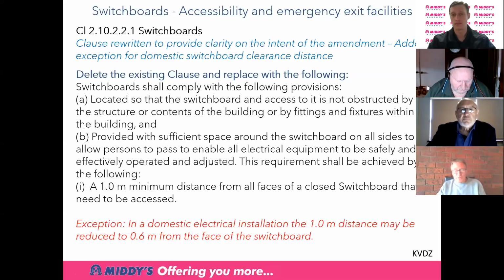Look, I'm doing switchboards, and if you look at clause 2.10.2.2.1, it's been totally rewritten to provide clarity on the intent of the clause. It's been split up into 3 parts now rather than 1. So you've got switchboards, switchboard rooms, and switchboard covers and doors. So we'll go into that. So we delete the whole clause and replace it.